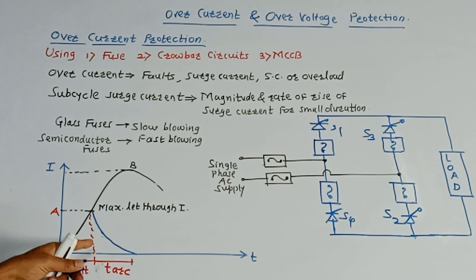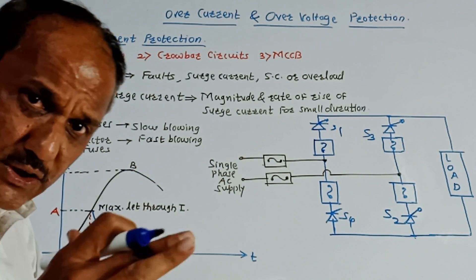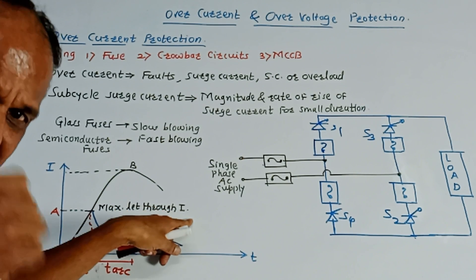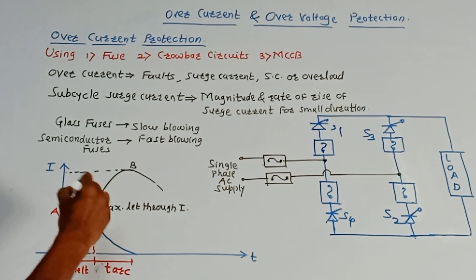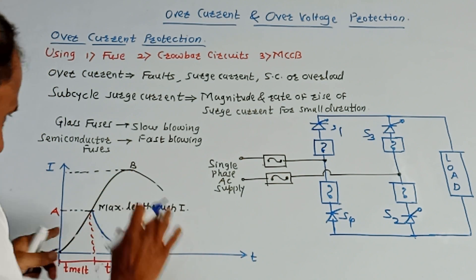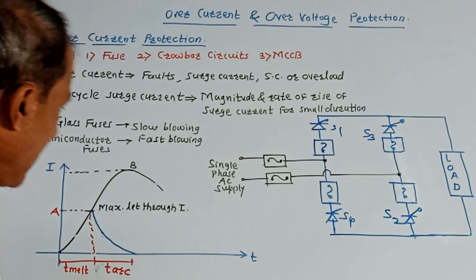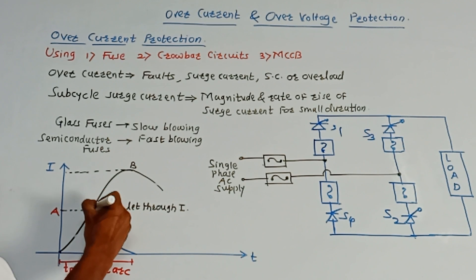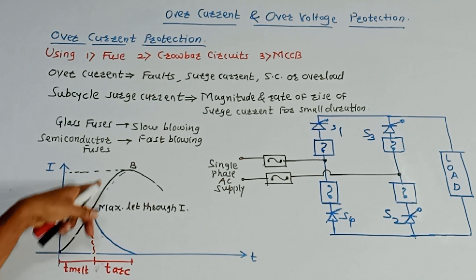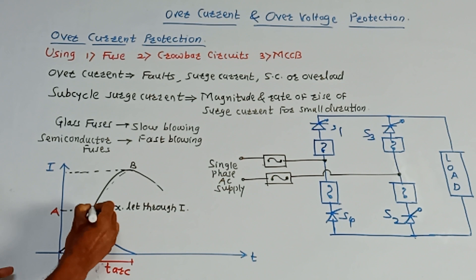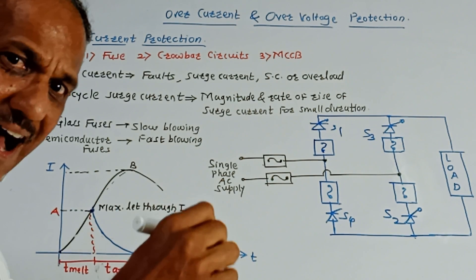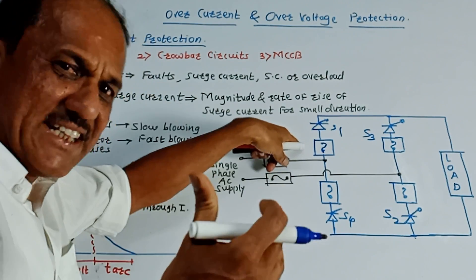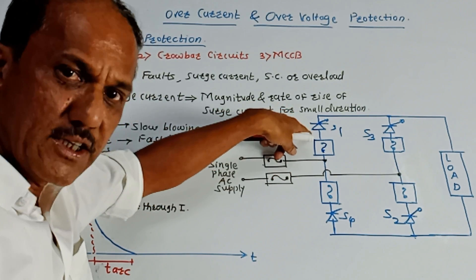This is the corresponding graph of current versus time, that is the current flowing through the fuse versus time. Point A indicates the maximum let-through current, that is maximum allowed current. Beyond that, if the current increases up to point B, point B indicates that the surge current may increase in the absence of a fuse. But due to use of fuse, once the current reaches up to point A, arcing between the fuse takes place. Because of this, the temperature gets increased and there will be an open circuit, which will protect the corresponding SCR.